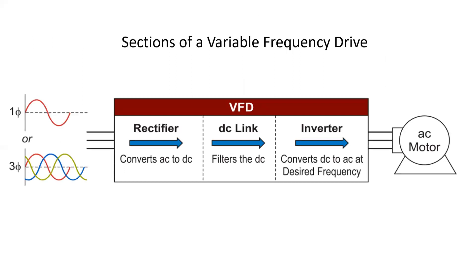The sections of a variable frequency drive are separated into three. Some VFDs are designed to take single-phase supply voltage and drive a three-phase AC motor — advantageous for running three-phase woodworking equipment at a residential acreage where only single phase is provided. Inside a VFD, we have a rectifying circuit which converts the incoming AC to DC, a DC link which is the DC bus where the voltage is filtered, and then the inverter section which converts DC to AC at whatever voltage and frequency is required.